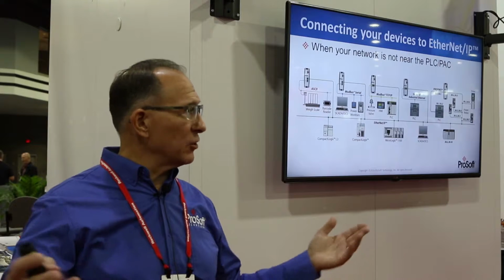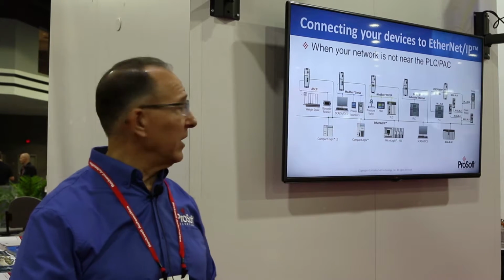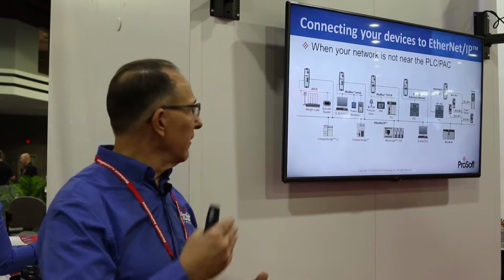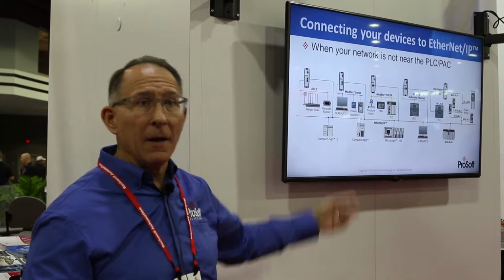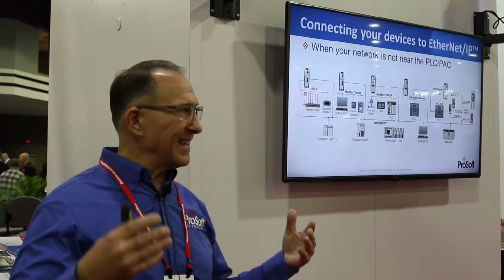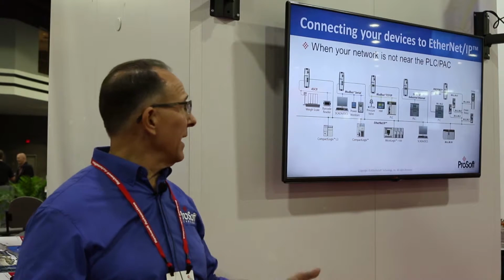There may be times where these devices and their networks aren't close to where the PLC is at. You may have Ethernet strung out there, but your device is talking on a serial Modbus network, and you don't have that serial cable all the way over to the PLC. We have a bunch of gateway solutions that allow you to integrate and bring in those different languages with the device data and pull that into the Rockwell architecture. Once that's all on Ethernet IP, you can, in one location, get all that information, start making good business decisions off of that, and gain value by reducing your downtime.